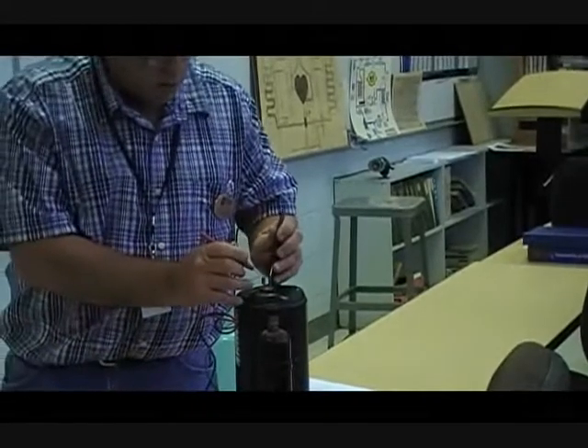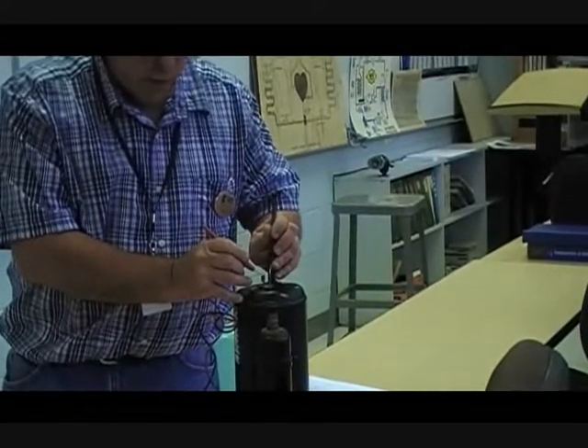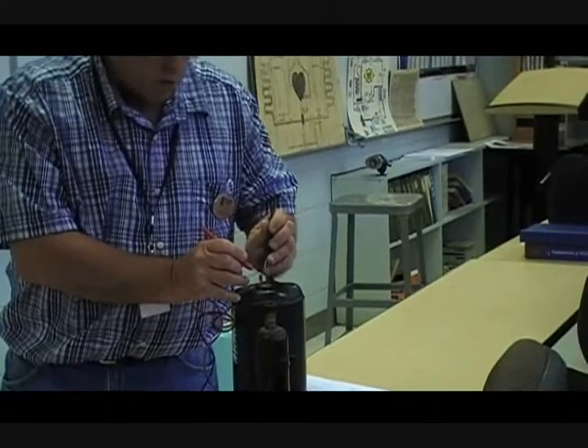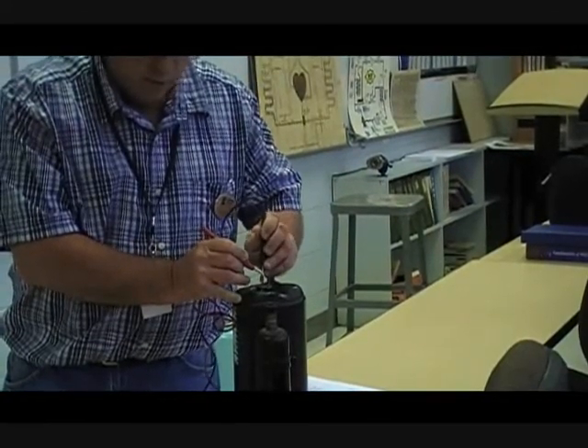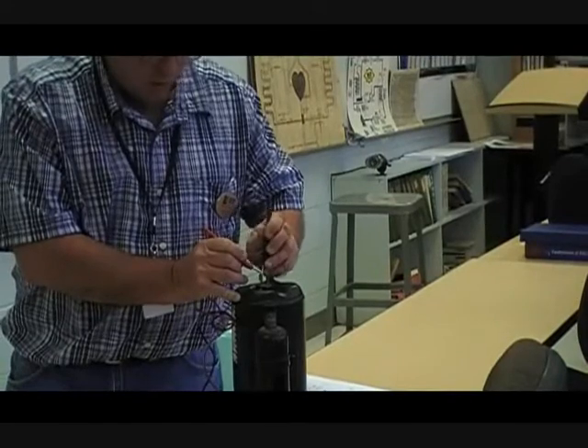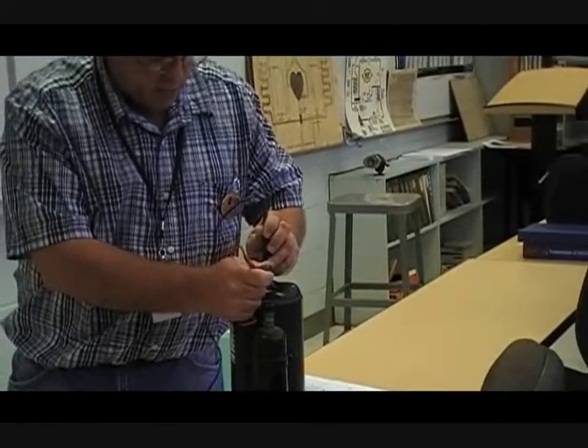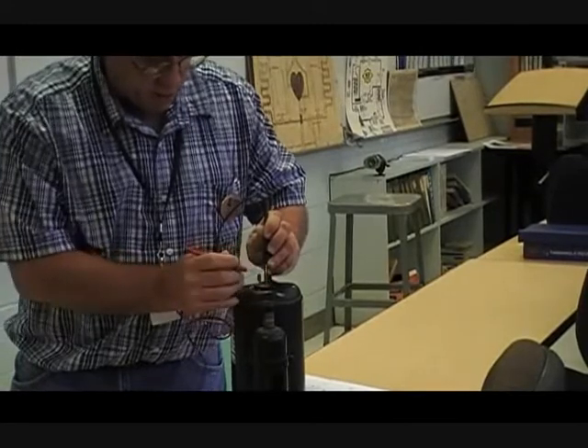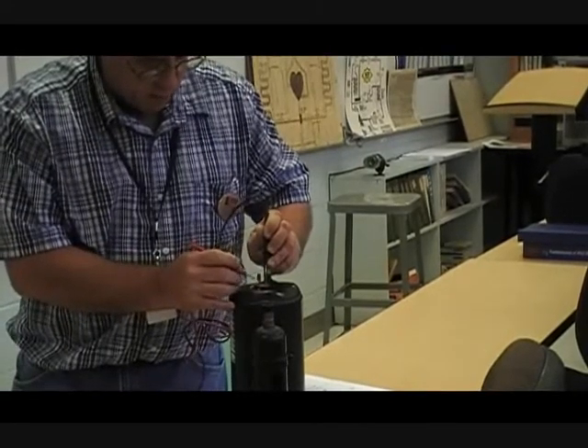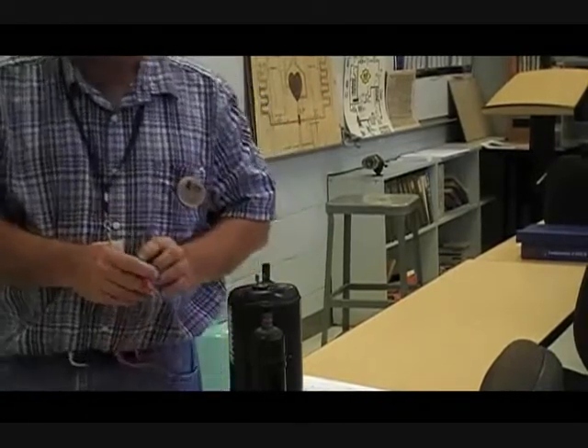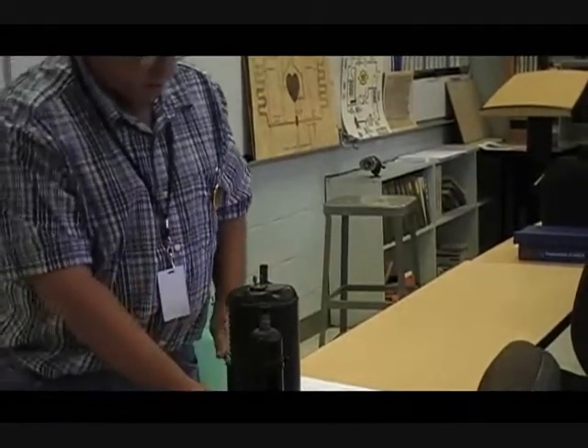The lower one of the two is going to be the run winding. So when I look at these two terminals, which two it was that I was on, that right there, this is now my run winding because it is not the one that we had a while ago, which makes the remaining one the start winding or start terminal.